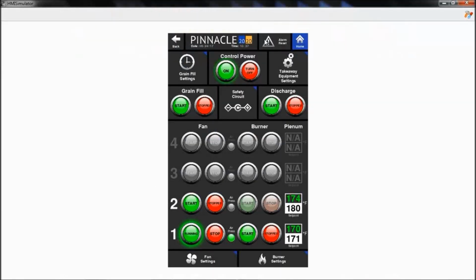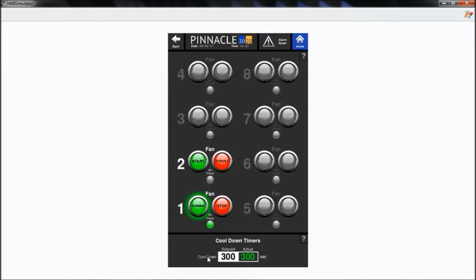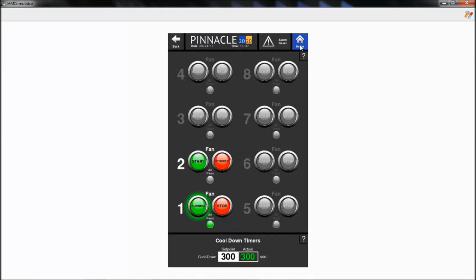So if we jump back here, we can see from our control screen, I have fan settings down below. If I click on fan settings, there's my cool down timer. The actual setting is a read value over here. I can't change that, but I can change the set point right here of 300 seconds. I can go anywhere between 0 and 500 seconds.